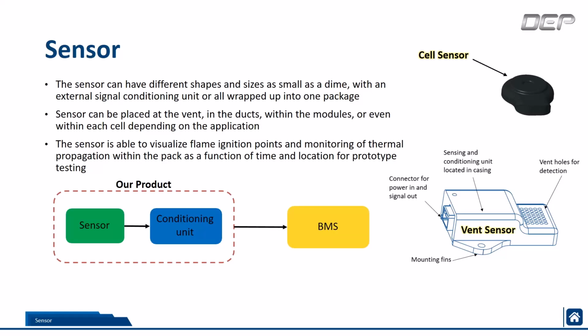Now for the cell sensor, the implementation requires a hole on the prismatic cell where the sensor will get welded, so it can get direct access to the internal chemistry of the cell. This will then be completely sealed, so there are no gases coming out before the seal breakage of the prismatic cell. Using this kind of detection method, our sensor can also visualize flame ignition points and monitor thermal propagation within the pack as a function of time and location. And this can be used for prototype testing.